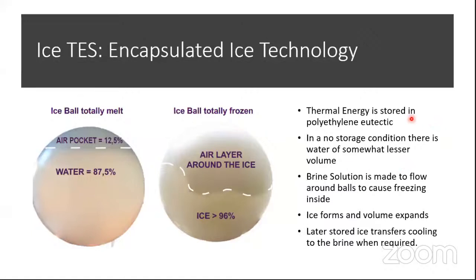And the thermal energy is stored in polyethylene eutectic balls, and in a no storage condition, like I explained, there is a somewhat lesser volume of water. Later the stored ice transfers cooling to the brine when required. So once the ice is formed, of course, the cooling can be extracted out of it by passing brine solution over them. We'll also understand more clearly what brine solution is later.